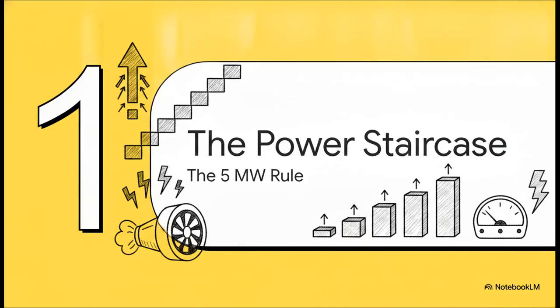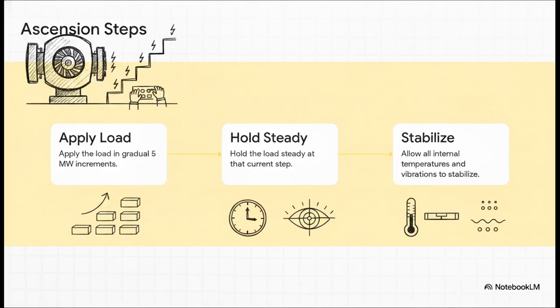This brings us to Section 1: climbing the power staircase, the 5 megawatt rule. Rather than a smooth, continuous ramp-up, the machine is loaded in gradual, distinct steps, commonly right around 5 megawatt increments. Operators apply the load, then hold steady at that step, watching the data like hawks, ensuring all internal temperatures and vibrations stabilize before asking the engine to climb even a little higher. It's a very deliberate, very patient rhythm.